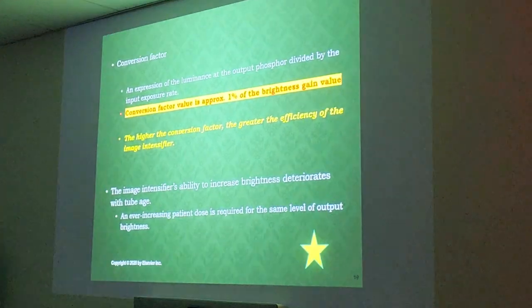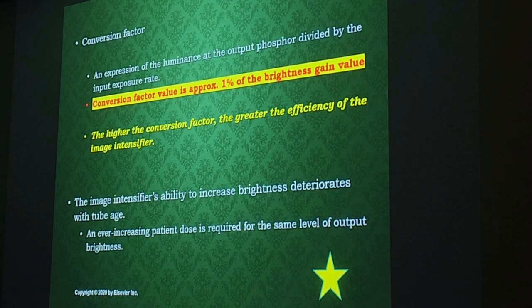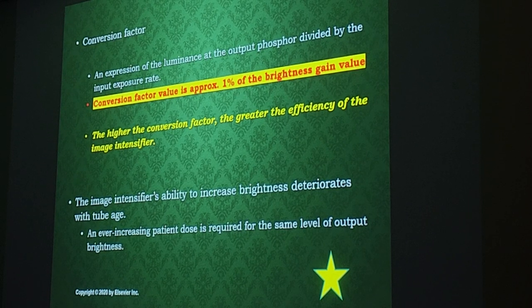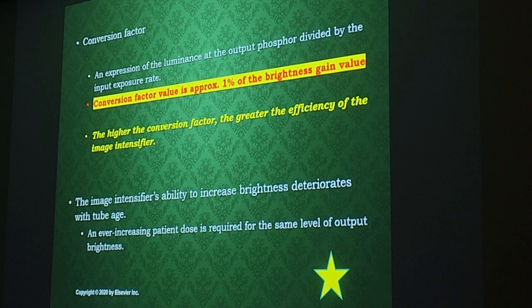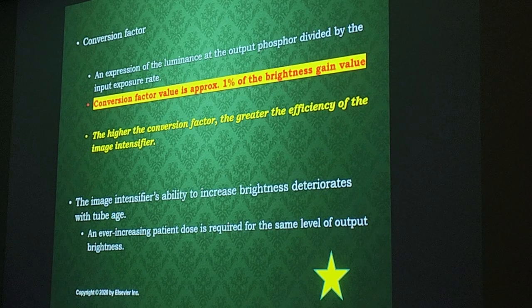We're going to continue on starting with the conversion factor and brightness gain — how are they related? The conversion factor is basically an expression of the luminance we get at the output phosphor divided by the exposure at the input phosphor. So it's calculating the gain and intensity we get at the output phosphor.